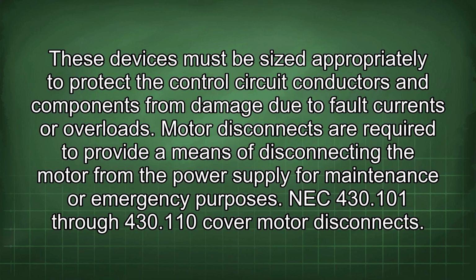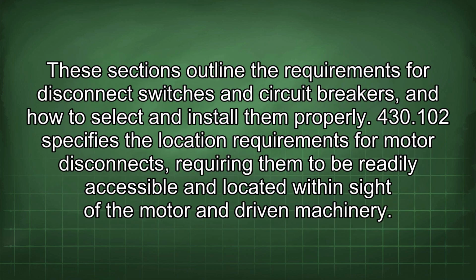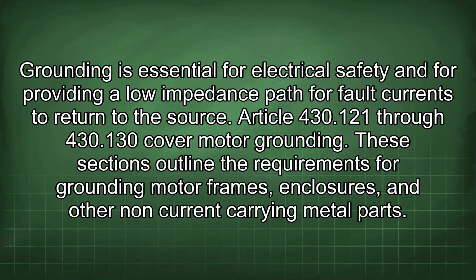or emergency purposes. NEC 430.101 through 430.110 cover motor disconnects. These sections outline the requirements for disconnect switches and circuit breakers, and how to select and install them properly. 430.102 specifies the location requirements for motor disconnects, requiring them to be readily accessible and located within sight of the motor and driven machinery. Grounding is essential for electrical safety and for providing a low impedance path for fault currents to return to the source.